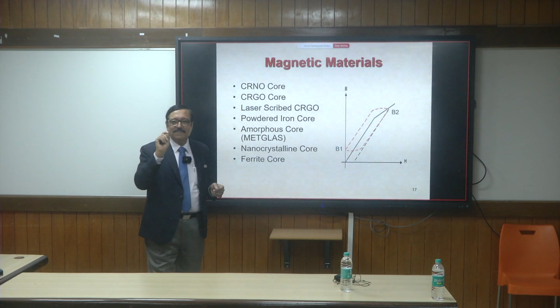Now ferrites have very low losses at higher frequencies, but unfortunately the flux density that you can permit in a typical ferrite core will not be more than 0.4 Weber per meter square typically, compared to about 1.5 Tesla or 1.5 Weber per meter square in a CRGO core. So you see the difference. Apparently the size becomes smaller, apparently, but no. When you take a sizing of a transformer, often in the electrical expressions we miss out the thermal aspects. It's not there in the electrical expression when you write E is equal to 4.44, etc.